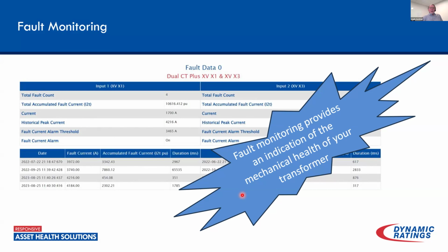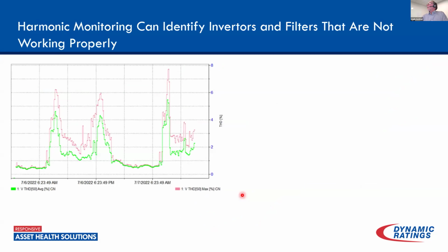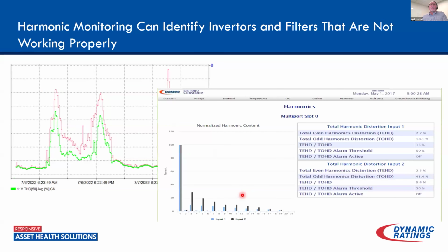Again, with the renewables, I expect the magnitudes are probably going to be less, but the number of faults is probably going to increase in that situation. We talked about harmonics, basically having some type of harmonic monitor on those transformers and the inverter-based applications. That is definitely a good idea.